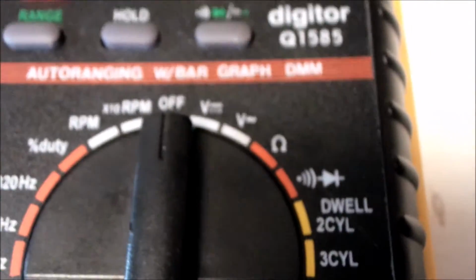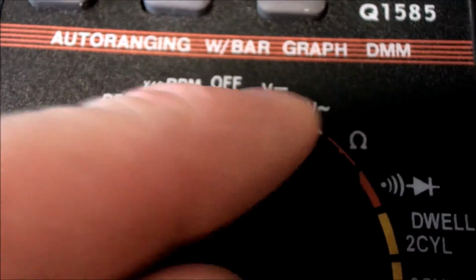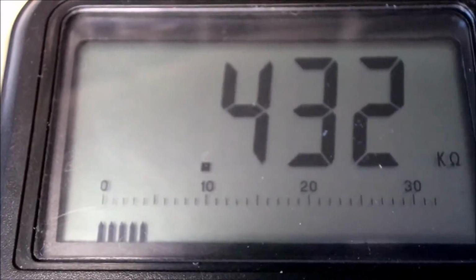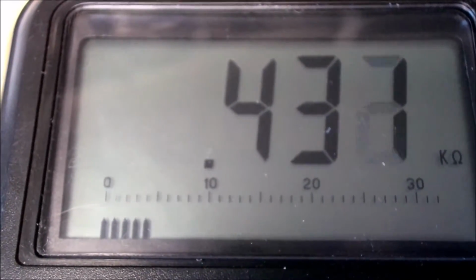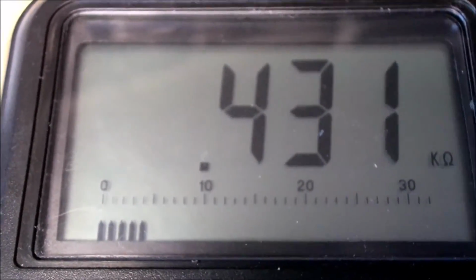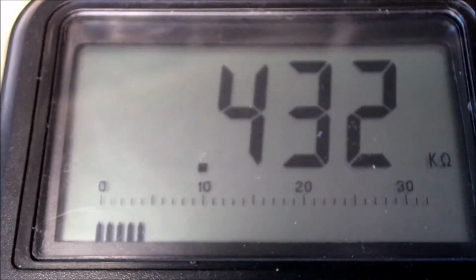So really all I need to do is check for continuity before I power it up, and the best way of doing that is I've just got my test leads on it. I'll come over to my multimeter and put it onto ohms, and we should have some sort of reading there, which we do. We have 0.4 of a kilo ohm. That's good, it's got continuity, so that means when I power it up - I've checked my diodes, they're okay - once I power it up I should get my 12 volts DC.